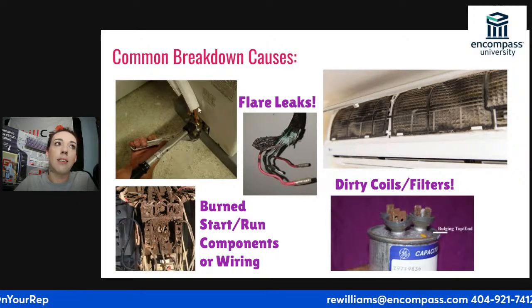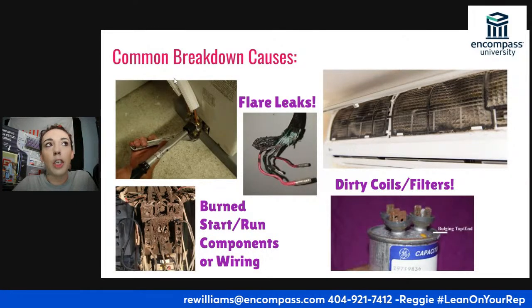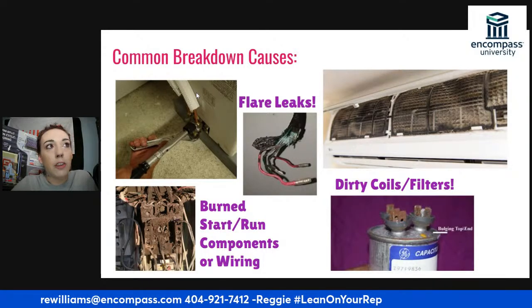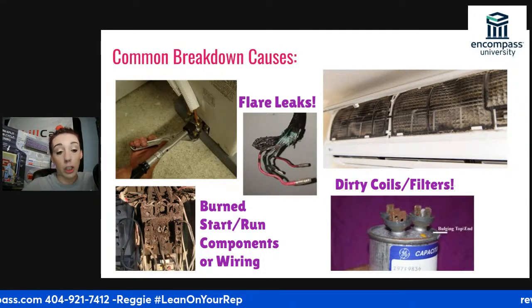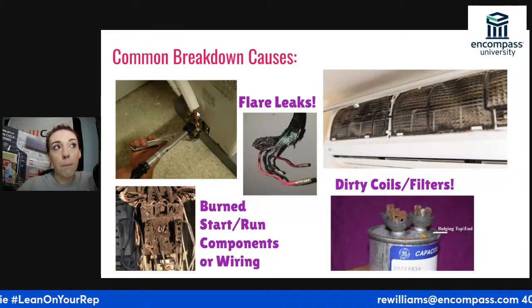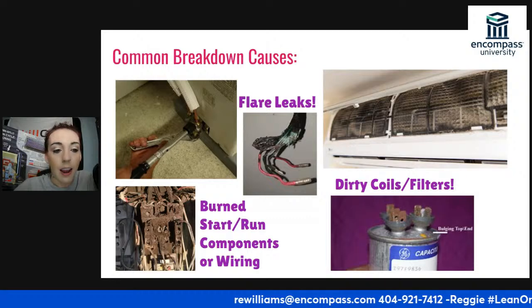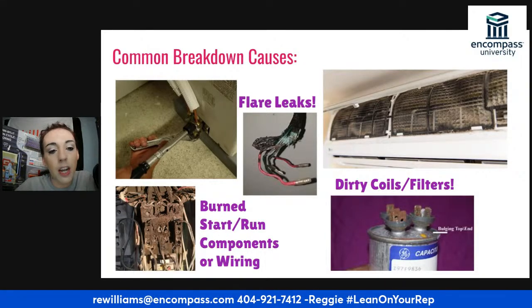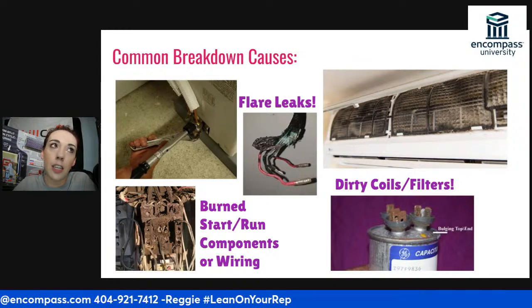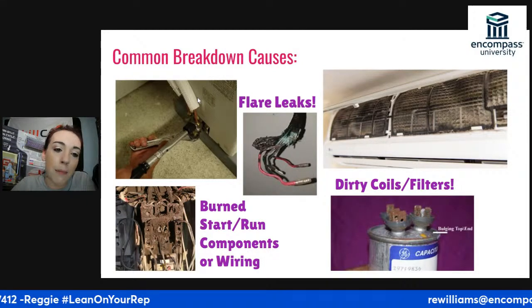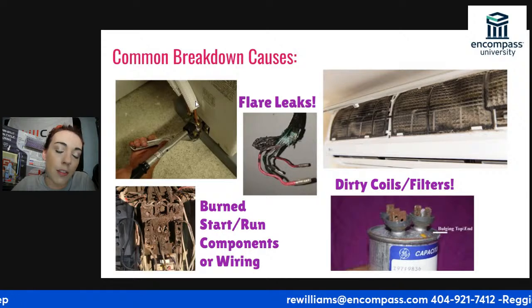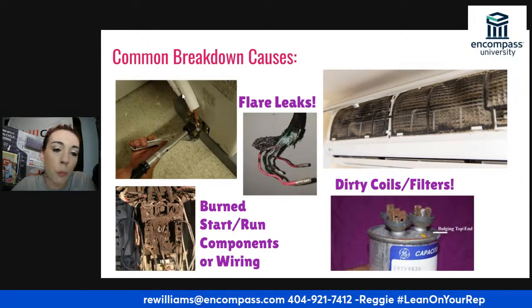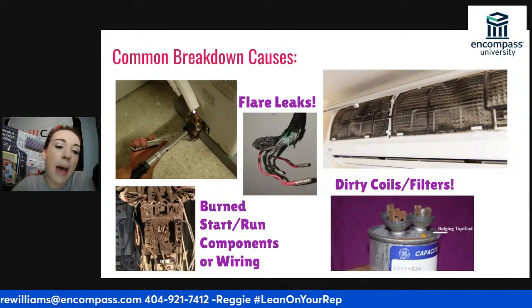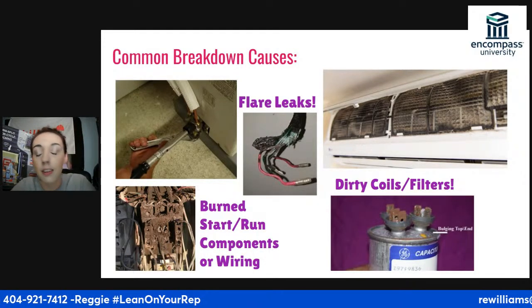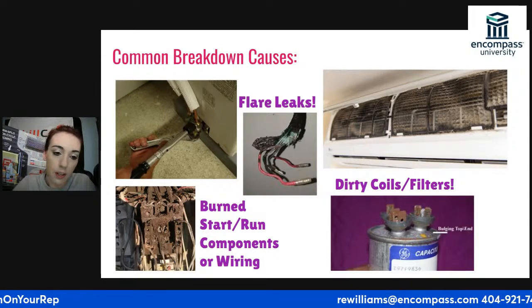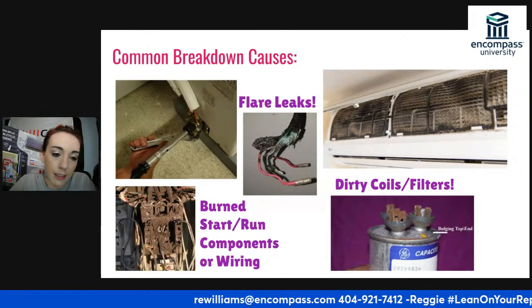Now, I just want to address this line set here. This white insulation has actually been recalled by many manufacturers that make it, because it has an enzyme in it from manufacturing that, when it touches copper over time, can cause pinhole leaks. It's corrosive in nature, but not corrosive like putting steel and copper together and leaving them that way. It is just an enzyme in this line set, a chemical that causes the copper to spring holes. So if you see this white line set when you come to a no cool call, pull that back and look under it and see if you find any holes, because usually that's the reason we've lost the charge in that case. We're using black or aluminum line set now.